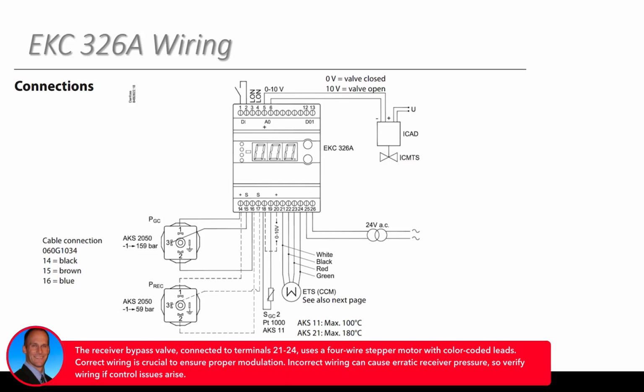If we're having problems right off the bat after an installation with receiver control, if the pressure's all over the place in the receiver, it could be that valve's just not modulating in the right direction because it wasn't wired properly to the device, whether it's an EKC or a pack controller. Yeah, so either like 22 and 23 mixed up, so your black and your red are opposite.